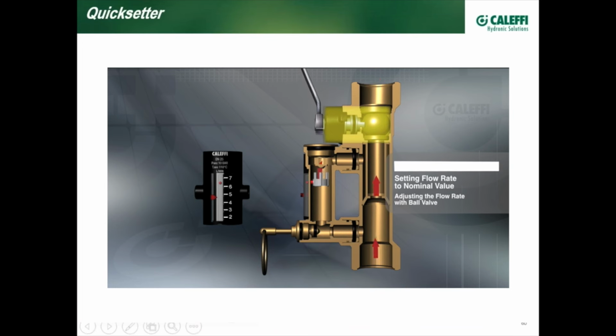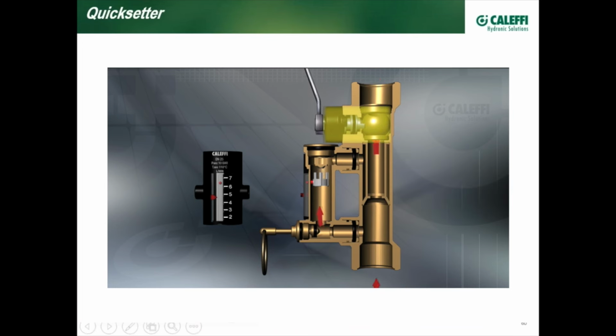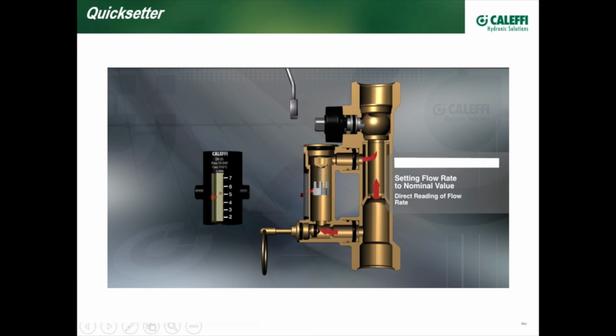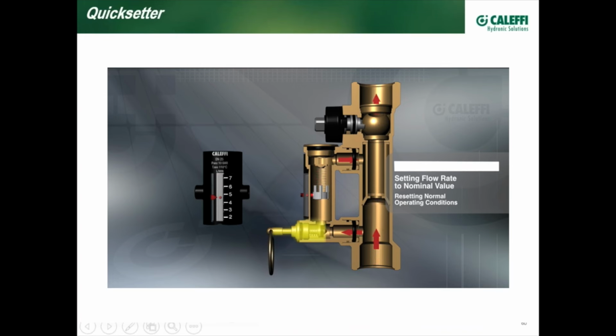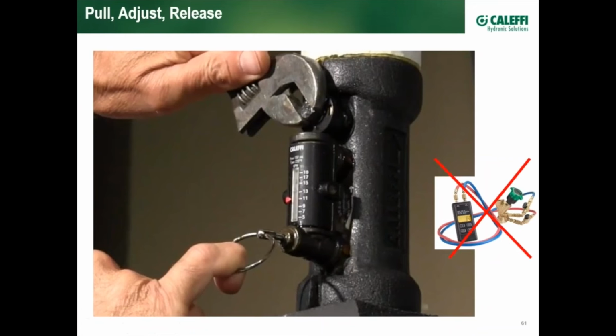So if the contractor, for example, wants 4.5 gallons per minute, pulls the pin, let's say it shows 6 gallons per minute, takes his wrench, adjusts the mechanism here to bring the flow from 6 down to 4.5, puts his memory indicator as shown here at 4.5, within seconds has set the flow rate versus having to worry about gauges. By the way, they all come with their own tailored insulation jacket, which is especially useful in chiller circuits to prevent condensation issues, such as this application on a chiller loop.